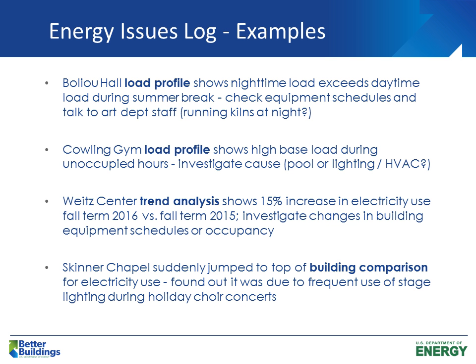There's the Skinner Chapel. We suddenly found out that our chapel had jumped to the top of that building comparison list. Well, it didn't take very long to realize that the performance schedule in that building had been very high over the last week. They were using a lot of stage lighting, and that was the cause of that. Now, that wasn't something we could necessarily fix immediately, but we can look at those stage lights for the future, and we also at least knew that it happened. It didn't escape us as facilities managers.